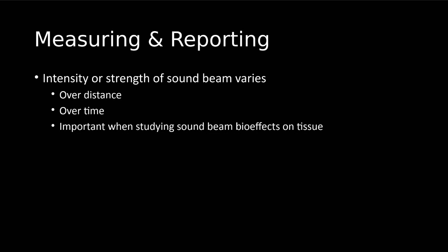Again, this is really important, particularly for OB scanning. We never want to be sending in an overwhelmingly strong sound beam when we're imaging a fetus, right? Those tissues are so fragile and so sensitive, and we don't want to have any biological impact on human tissue if we don't need to. So this is something that is done behind the scenes in terms of working clinically, but you need to be aware of it as an operator of these systems, and why it's so important to continuously be getting preventative maintenance done on our machines.